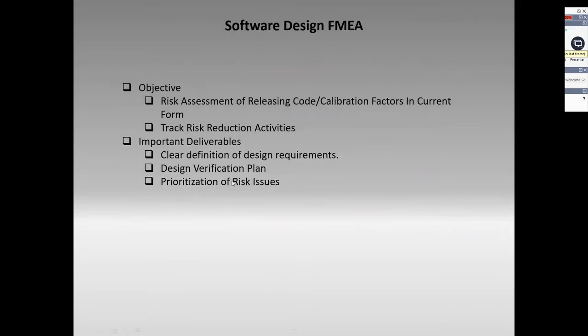So, software design FMEA: the number one objective is we want to do a risk assessment of releasing the code and calibration factors in its current form. And if we make changes to the code and calibration factors, I want to track all those changes that we did.